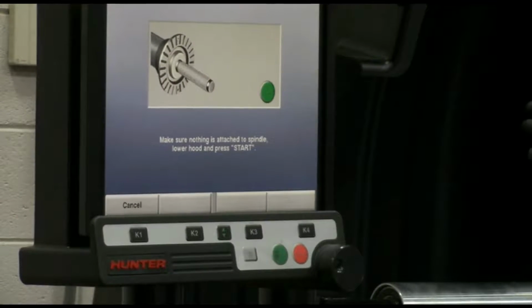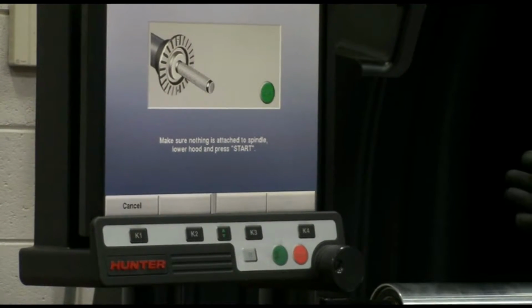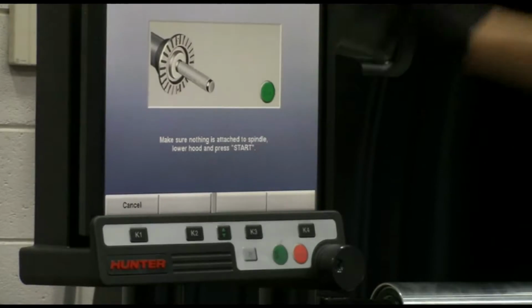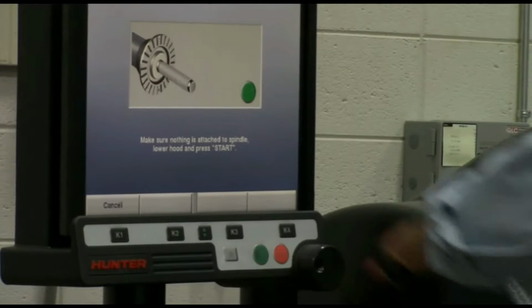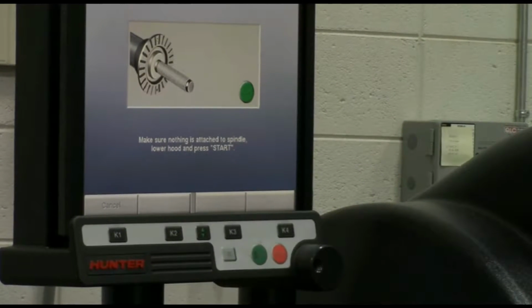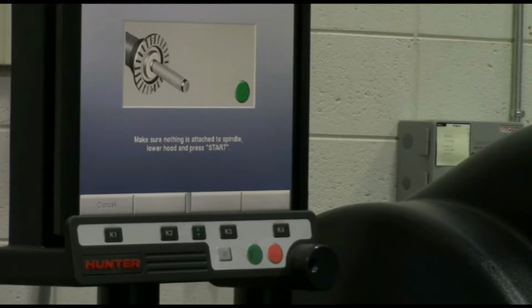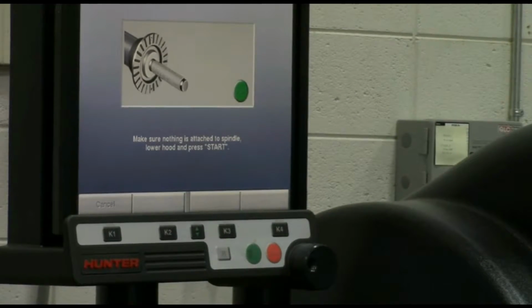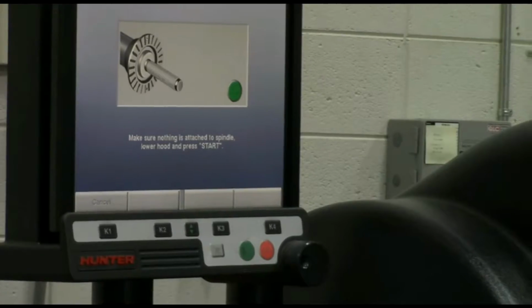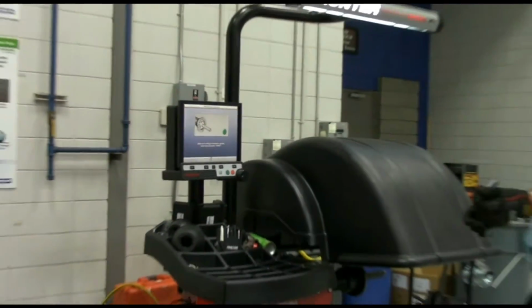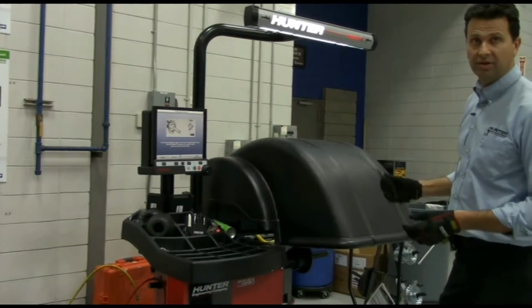This is what we call RFS technology. You read the screen and it tells you exactly what to do. So it says make sure nothing's attached to the spindle, lower the hood and press start. The machine is so quiet you don't even know that it's running. You have to look down there visually to see it. But we'll spin without the weight, and then we're going to spin with the weight on the left-hand side of the hub and then the right-hand side of the hub.